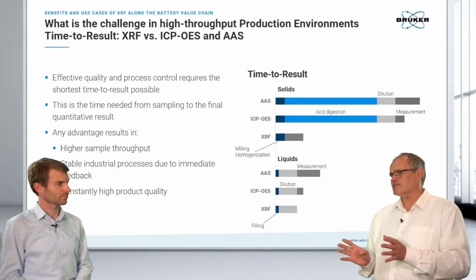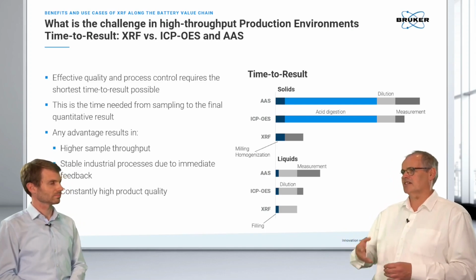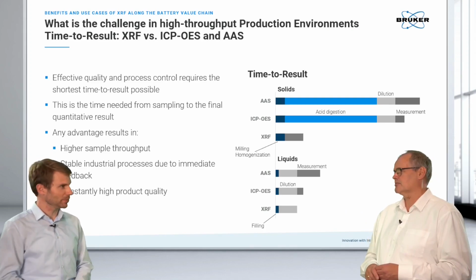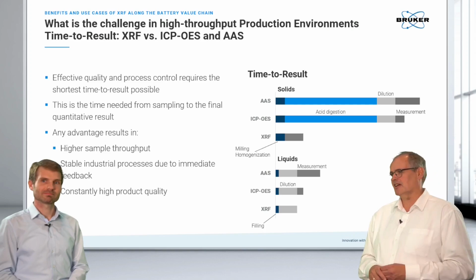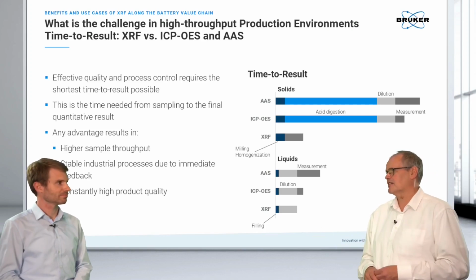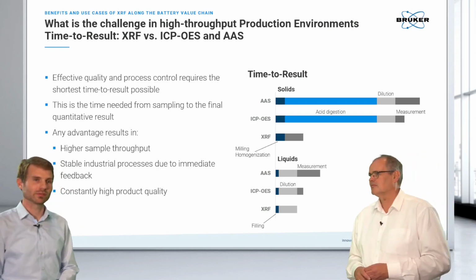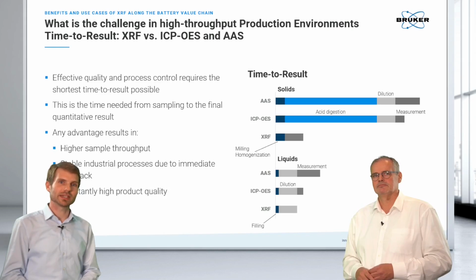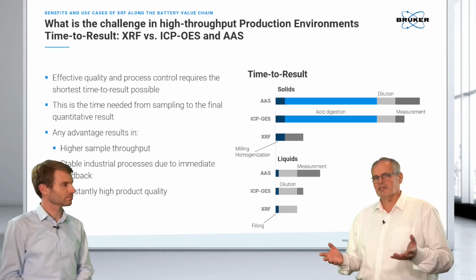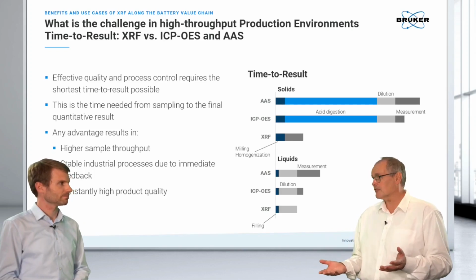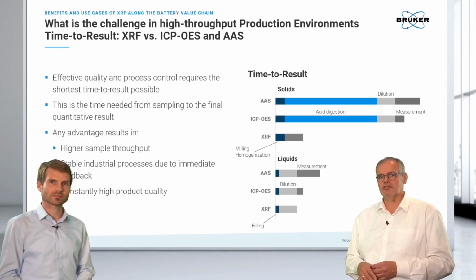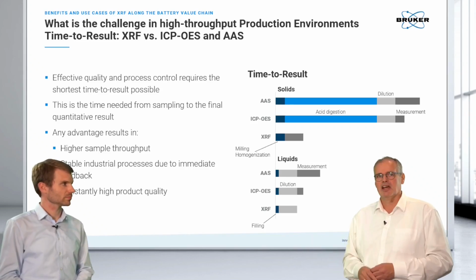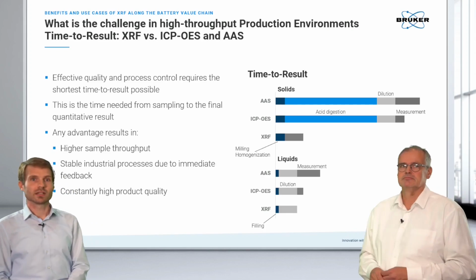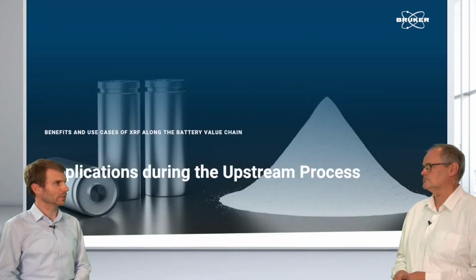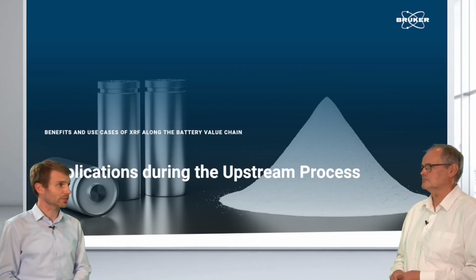For liquids, the advantage is not so big, but nevertheless, you need to start the instrument, you need to calibrate, and you need to dilute the sample, and with XRF, you simply put it in, and that's it. Yeah, the calibration is valid for a very long time, and you can even facilitate 24/7 monitoring here. So in total, much higher sample throughput and a long-term calibration. You invest effort once and then you are done. And then we ensure the shortest time to result, which helps in production. Exactly. So now let's dive into some real examples, really more from the upstream production process, Kai.